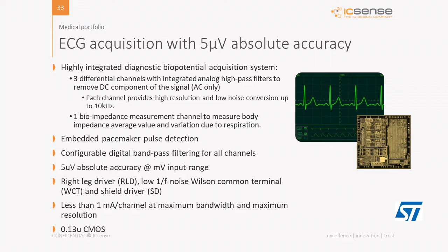And then another example is the ECG acquisition chip that we have developed for ST. With this chip, you could measure a lot of highly integrated diagnostic biopotential signals. So we were able to do ECG and also other biopotential measurements. The bioimpedance measurement was also one of the signals that could be measured. There was a configurable band-pass filtering, also with the right leg driver, the Wilson common terminals, and the shield drivers were measured with this chip.